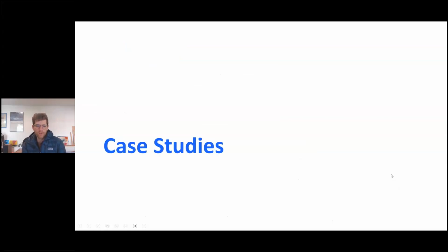So I have a number of case studies from sites that we've deployed at. We've done about 16 projects to date. All of these case studies will be from supermarket refrigeration systems as a way to save energy and provide capacity. One of the sites is an HFC refrigeration system, so it uses R404A, a more traditional cooling cycle. We have one set of case studies with CO2 as the refrigerant, so these are transcritical CO2 systems, and then one evaporative cooling case study where we installed sensors to measure how much water the condenser is using, and then quantified how much water savings we had from our system. And then I have a case study from a data center that we put together, and I can talk about the integration potential there.